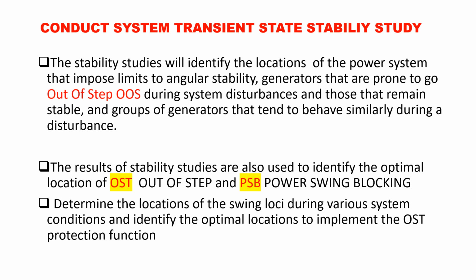So what is done? The tripping is carried out through the relay setting. As a result of the power system transient state stability studies, the tripping is fixed at those points, and if you trip the breakers, then the system will be in an islanding mode, and the two or three power plants can be run with a specific loading. They will not be overloaded due to the power swing or the disturbance tripping, etc. So you can have a power swing blocking for that period also, or you can have out of step tripping as well. It is up to us. Whatever we want to do, we can do that. And these points you can get from the power system transient stability studies.